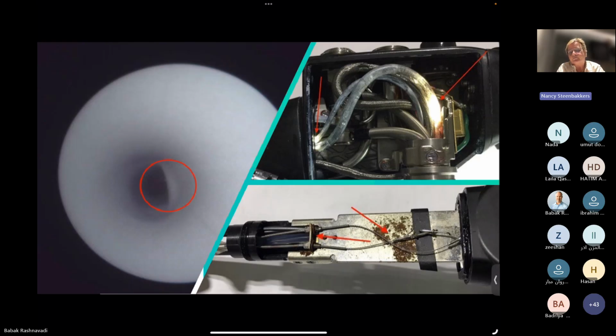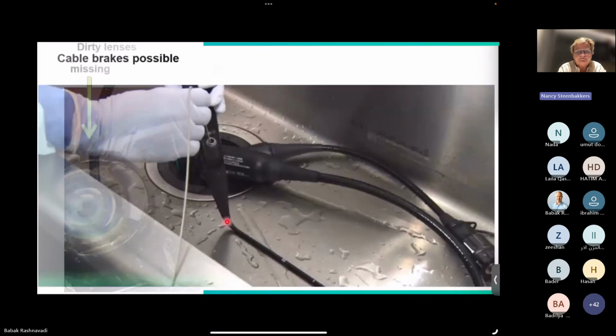In the other pictures it is also the same: you see corrosion appearing very easily. Next, please. And then here you can see also that if you have a small and tiny sink and you have to brush, you can easily break the cable, because of course you have to brush, but if you're handling it and the corner is too tight, then you're breaking the cable again. So this is also a high cost of repair. Next, please.